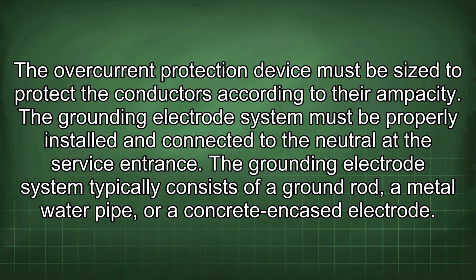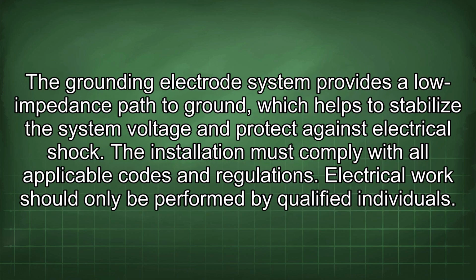The grounding electrode system must be properly installed and connected to the neutral at the service entrance. The grounding electrode system typically consists of a ground rod, a metal water pipe, or a concrete encased electrode. The grounding electrode system provides a low impedance path to ground, which helps to stabilize the system voltage and protect against electrical shock. The installation must comply with all applicable codes and regulations.